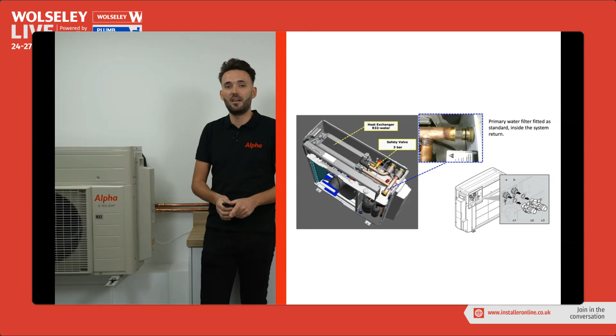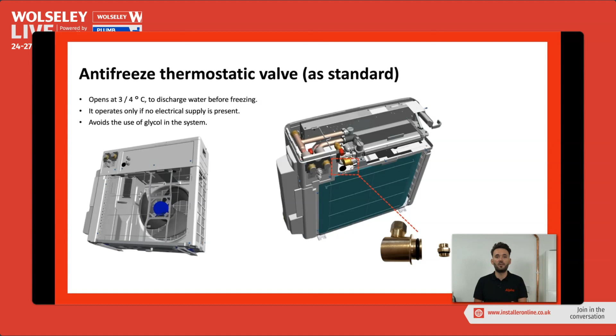We also supply with the kit what's called an antifreeze thermostatic valve. With heat pump systems in general, you have to put what's called glycol into the system, similar to antifreeze, and that's to protect the outside pipework and the outside heat pump. Now, with fitting our valve, you don't need to put glycol in the system. So for installers that are worried about dosing the system with glycol and how they maintain that glycol within the system, you can fit the valve and put normal heating water through the system. So that's kind of how it works.